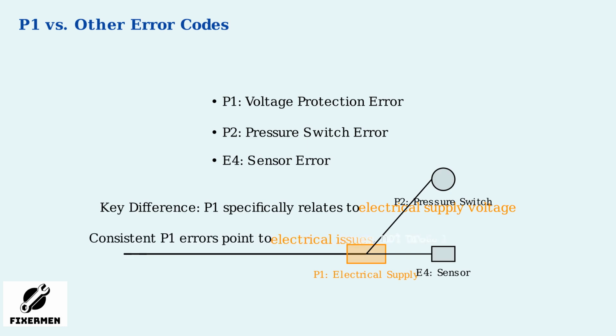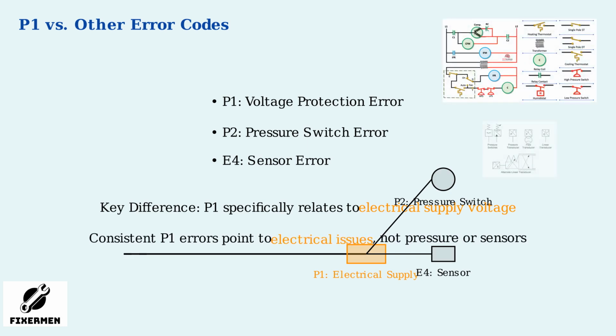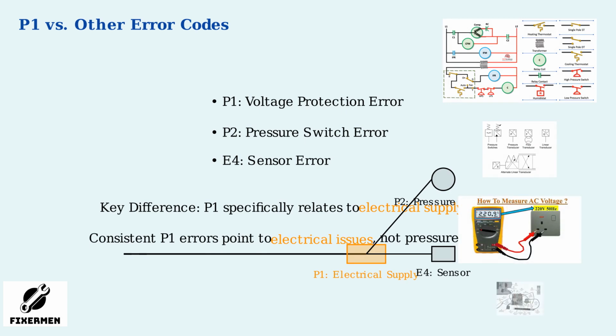When troubleshooting P1 errors, concentrate on electrical aspects such as wiring, transformers, and voltage stability. Check the power supply first, as P1 is designed to protect against voltage fluctuations that could damage the system. In contrast, P2 errors require checking pressure switches and refrigerant levels, while E4 needs sensor inspection and calibration. Understanding these distinctions helps direct your troubleshooting efforts effectively.